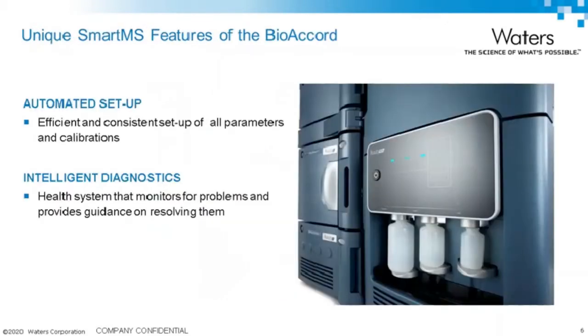There are 2 unique features of the BioAccord system: automated setup and intelligent diagnostics. All common tasks needed for instrument setup, including calibration, tuning, and resolution check, are set up automatically. In front of the instrument, there are 3 solutions containing the calibration solution, the wash solution, and the lock mass solution. In addition, the instrument contains a built-in health system that monitors for problems and provides guidance on resolving them.